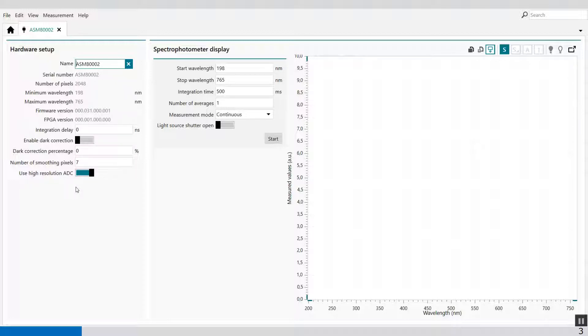The high resolution ADC is a toggle which can be used to enable or disable the high resolution analog to digital conversion of the spectrophotometer. When enabled, the measured values are resolved using a 16-bit analog to digital conversion. When disabled, a 14-bit analog to digital conversion is used instead. The default value is on. So this is my hardware setup of the spectrophotometer.